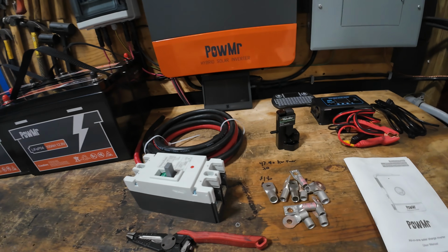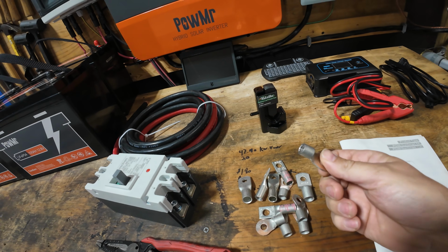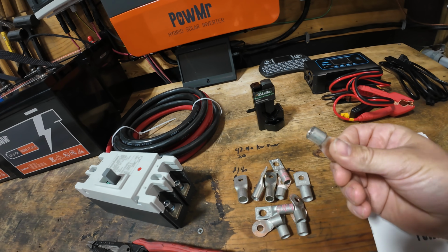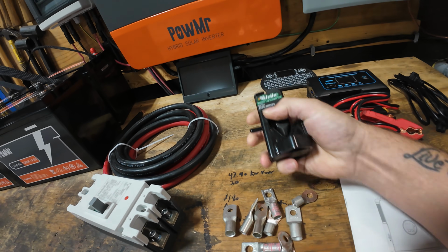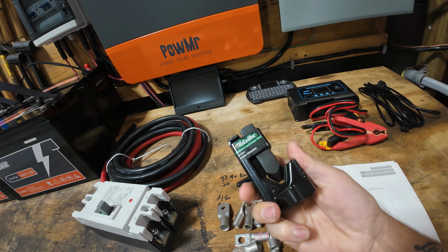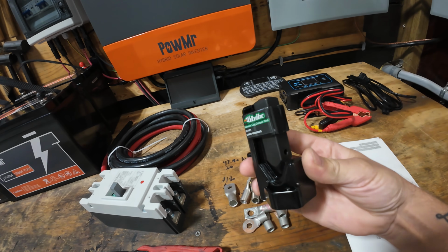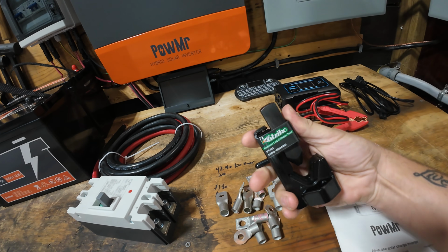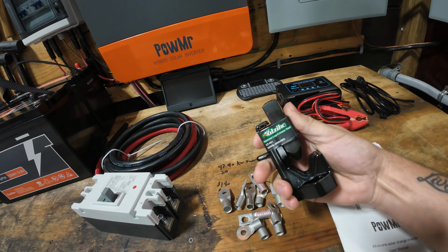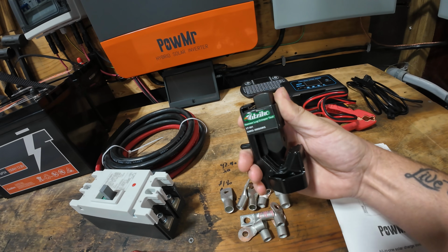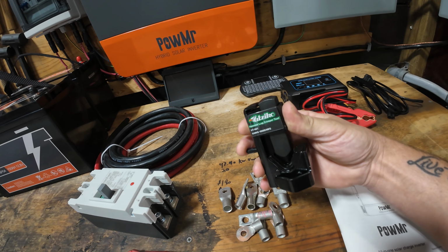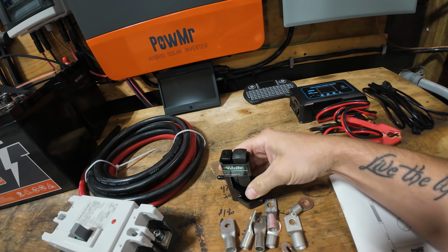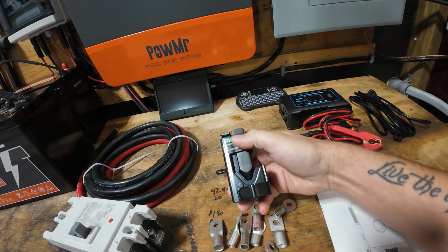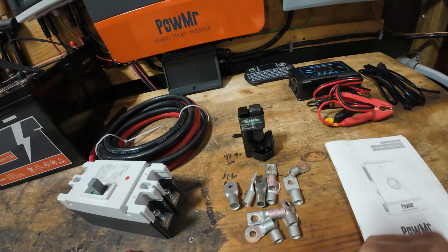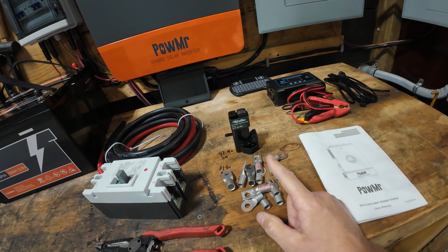Another thing you guys are going to need is a way to crimp these big cable eyelets. I didn't have a crimper that was large enough, so I ended up finding this online - I think I bought this off Amazon as well, it's like $13, called a hammer crimp. It's got a spring that holds this top part here, and you'll set the eyelet inside of here. You release the spring tension, which will hold the eyelet in place, and then you set it down on a nice hard surface and give it a smack with a hammer. Boom, there you go - you've got a nice crimp connector, and I hear these work very well. A lot of people are using these.